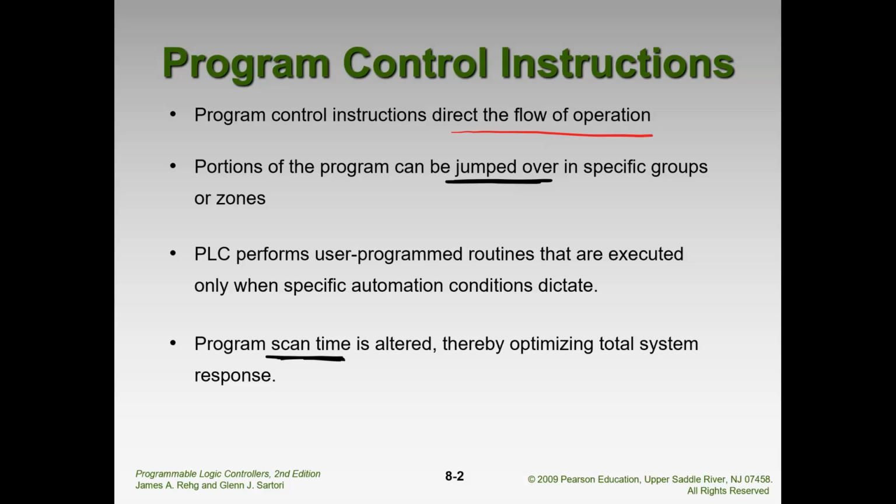So whenever you're using program control instructions, it is very important to remember that you have to think about your scan time and make sure that you are using these instructions in order to optimize your total system response and you're not making it worse. Sometimes when you are using the repeating part, you might get stuck in a loop and it makes your scan cycle go on forever. So you cannot come out of this loop.